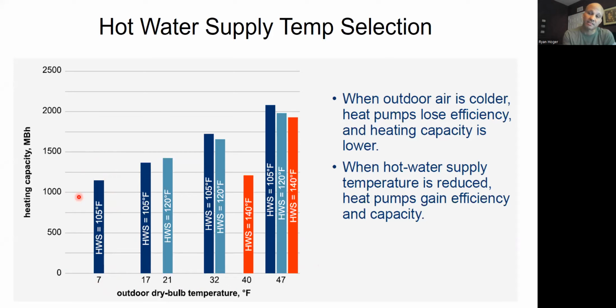But then maybe the boiler has to take the 105 and heat it up the rest of the way for me. I'm still taking load off the boiler. All these heat recovery machines are taking load off of the boiler, and they're using waste cooling to do it, which is fantastic.